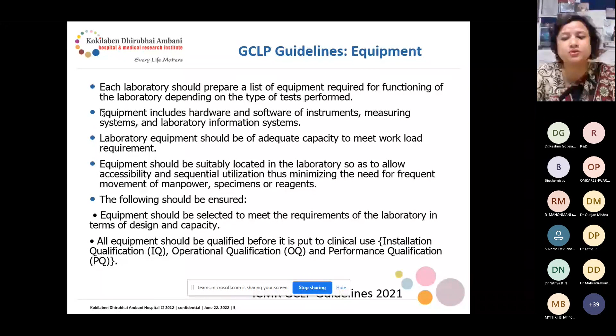All equipment should undergo calibration and verification. Performing the calibration process involves applying a standard value to the lab instrument and observing how it behaves. Calibration frequency should be as defined by the manufacturer or as per the norm. In the case of examination systems such as automated analyzers, the calibration should be done by the manufacturer, or many times during PM, preventive maintenance, they do the calibration. All the automated examination systems, such as cell counters, clinical biochemistry autoanalyzers, automated coagulometers, ELISA readers, everything in the lab shall be calibrated at regular intervals as per SOP. And raw data generated during the calibration should be maintained as a record. So like yesterday, I was going through the CAP checklist.